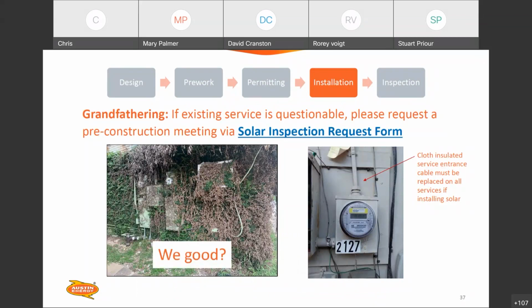So grandfathering systems, and what can you grandfather? What needs to be updated? Picture on the right here. So cloth insulated service entrance cables must be replaced on all services if installing solar. So there is no scenario in which we can allow that ragtop, as the old guys have called it. That needs to be updated. If you see that on a service, just include that in the cost of the project, because you will need to redo that service. You'll need to pull a separate permit, and you'll need to get that upgraded before you can tie in the solar.